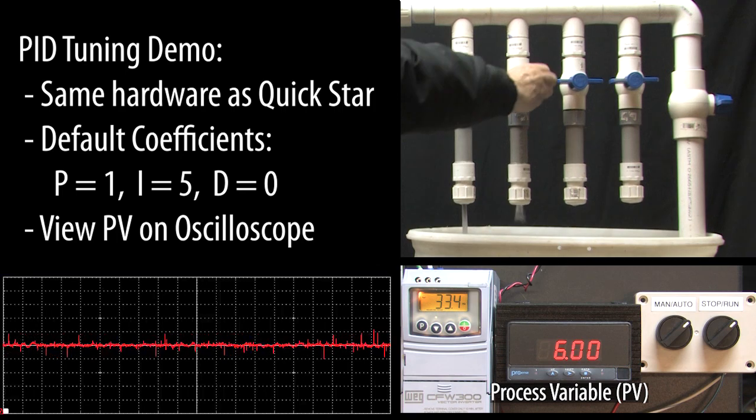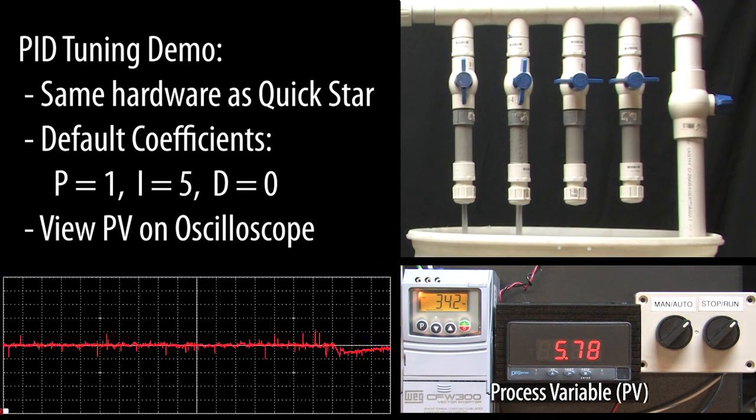We're at 6 psi and the drive output is at about 33.4 Hz. I'll open a valve and we see the pressure drop and then slowly climb back up to 6 psi over 10-15 seconds.